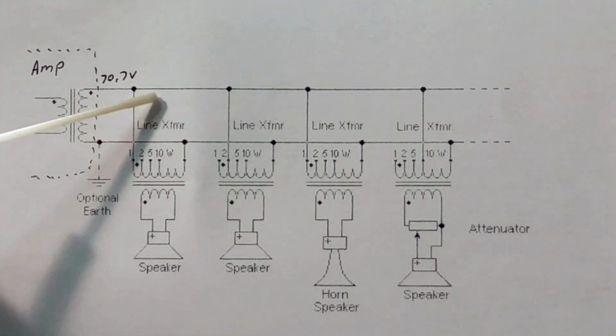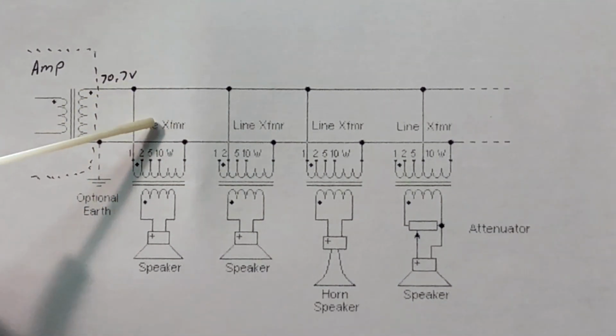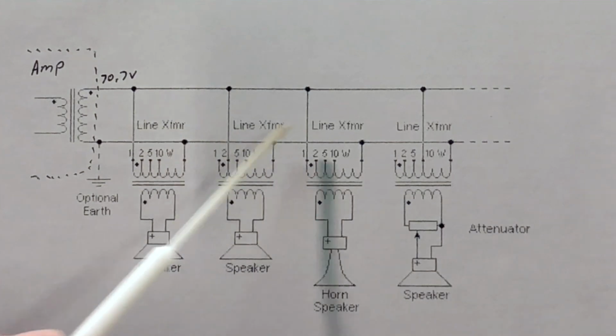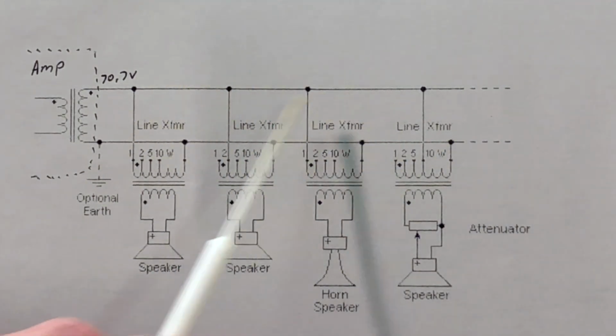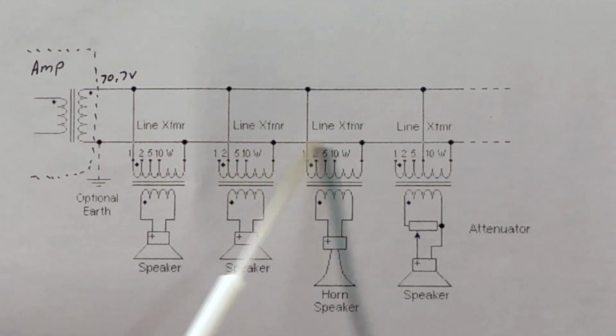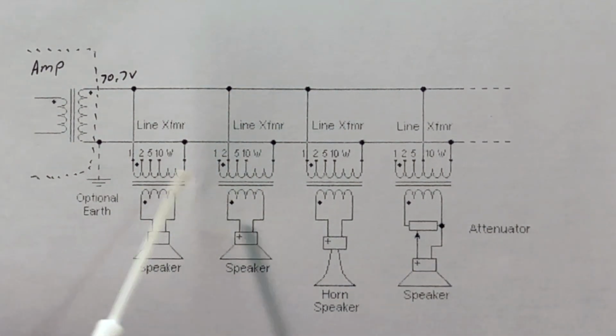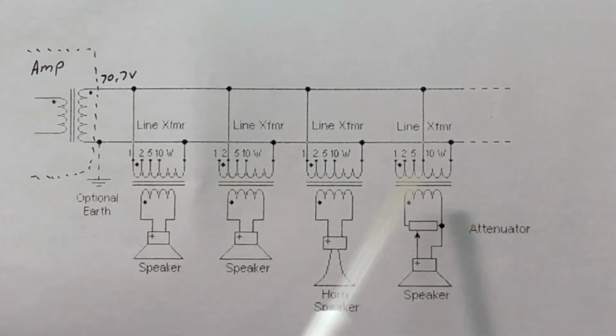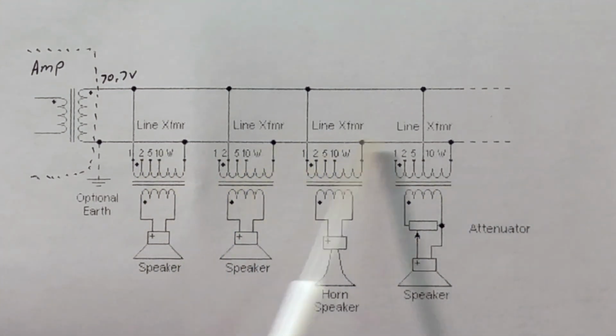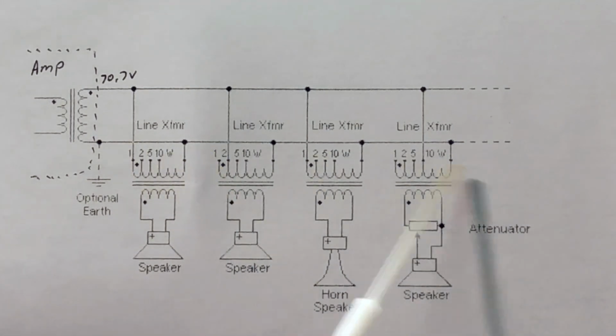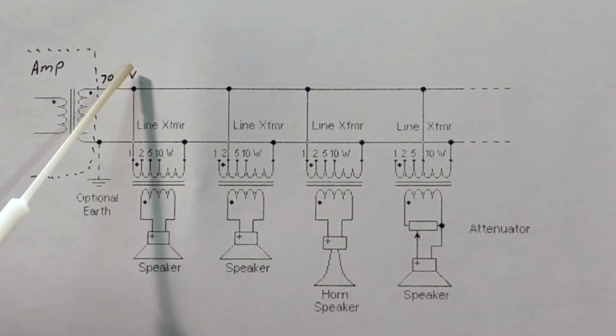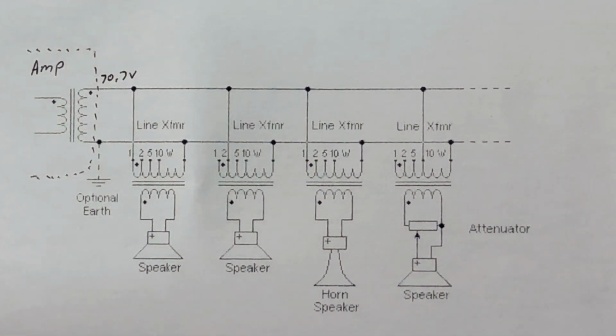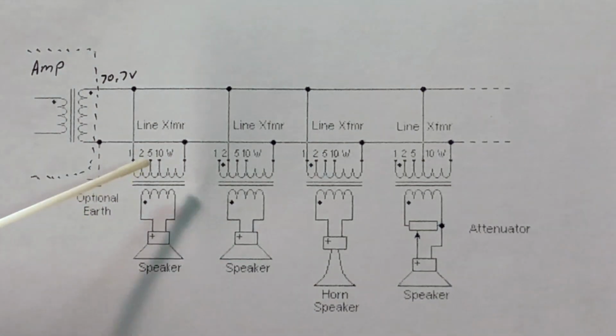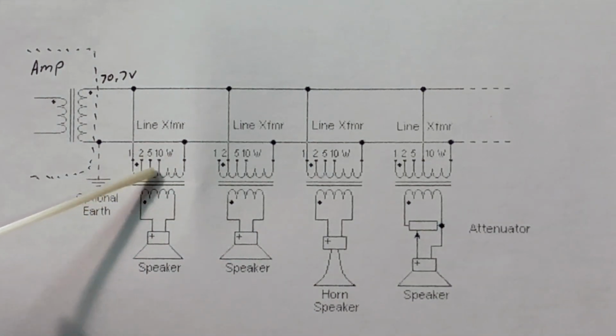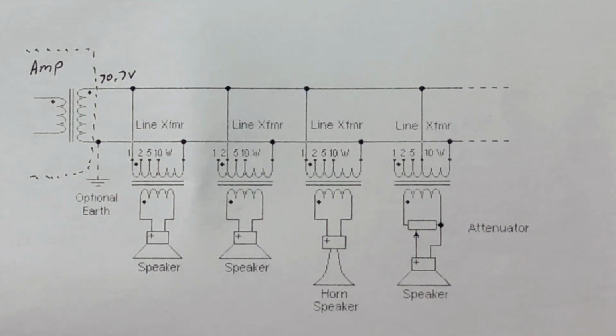Because the impedance is high, the voltage rises and the current falls, and that makes this distributed system work very well, because these wires coming out here could be 14 gauge or 16 gauge, something very manageable. They don't need to be a real heavy gauge of wire, even though you may have 100 watts or 200 watts or so of total power being delivered to the loads out here. Again, because the voltage is high, the current is low. Each of these transformers represents one like the example we're using in the test here.